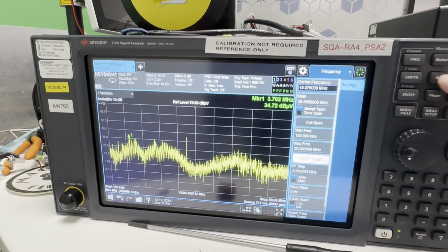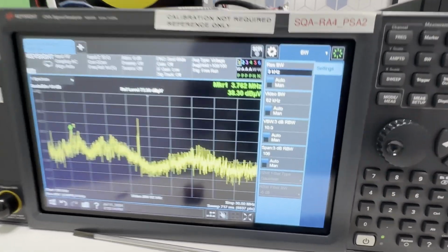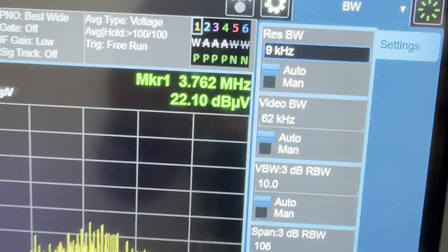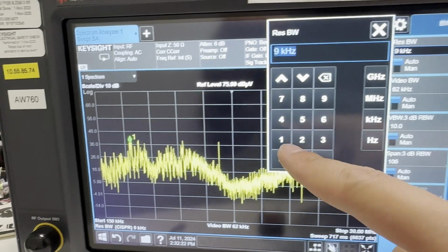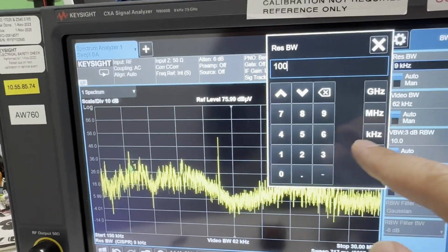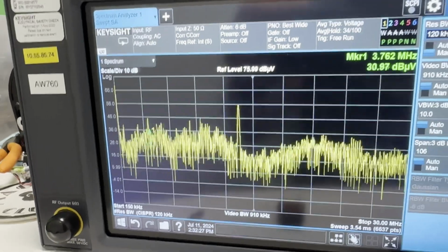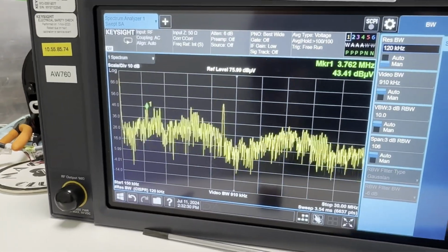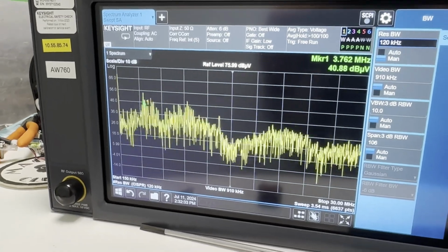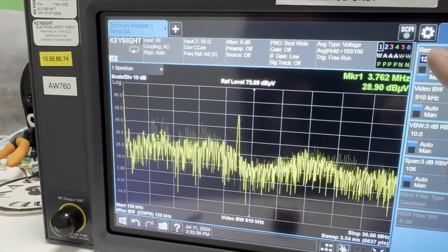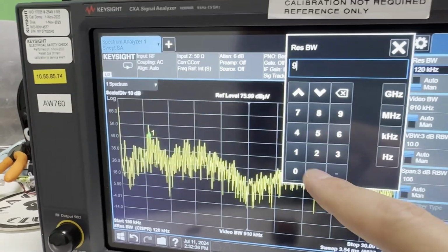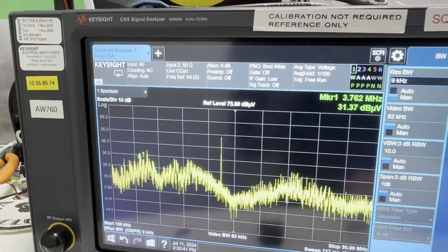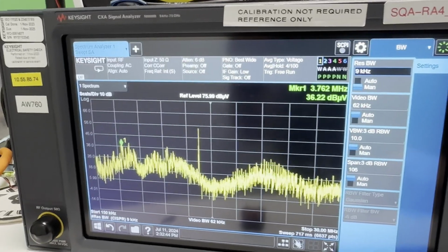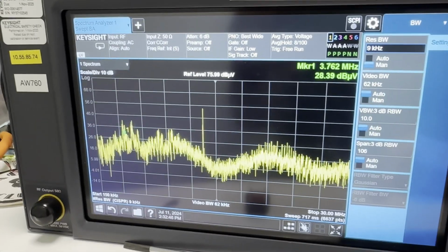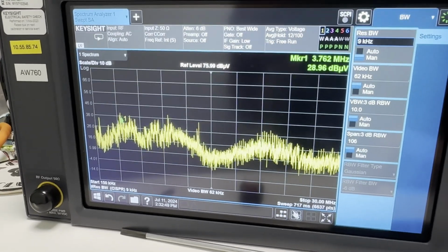Then you would also need to set up the bandwidth, and the resolution bandwidth is very important; set it to 9 kilohertz here. Sometimes you can have it at 100 kilohertz, and you will see that it runs much faster. It takes a lot less time to go through, but the resolution is not going to be as detailed. So 9 kilohertz is really good to set, because this is also in the standard, for low frequency.